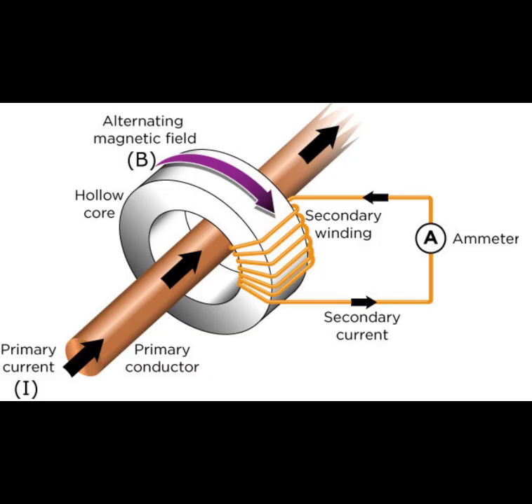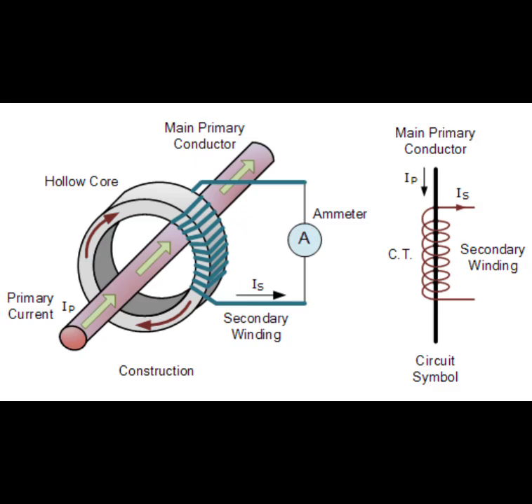The induced current in the secondary is directly related to the primary current and is governed by the ratio of turns between the two windings. The ratio of the primary current to the maximum current the measuring instruments can handle determines the current transformer's turns ratio. Typically, the secondary current in such transformers is standardized at 5 amps.